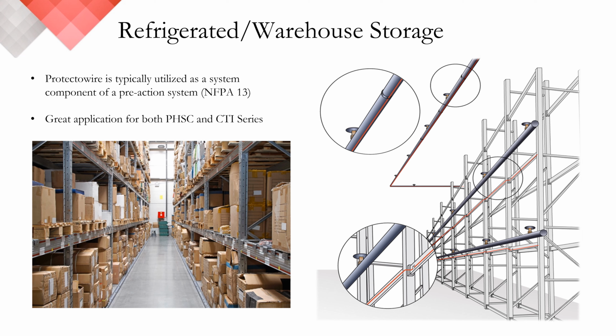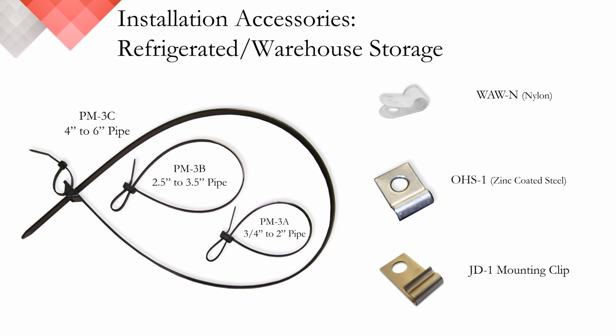However, in a manually operated and active storage facility, the in-rack sprinklers take an incredible amount of abuse. This is the one area we recommend keeping the detector off the sprinkler pipe and as far out of harm's way as possible. With this level of exposure, it's not a matter of if, but when the detector will be compromised. Again, as a digital contact device, the PHSC series does not have the ability to distinguish between heat and physical damage, which is why CTI should be considered in these applications. Providing the ability to know the temperature at the spot of the fault will avoid costly false alarms. Of course, this is specific to in-rack detection.